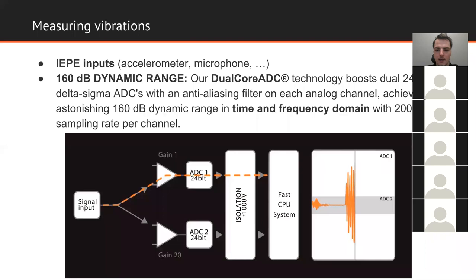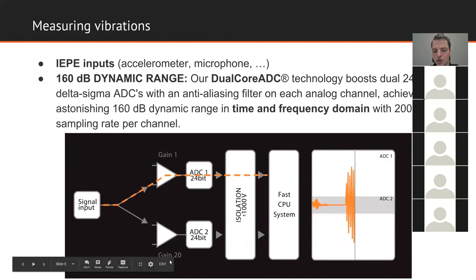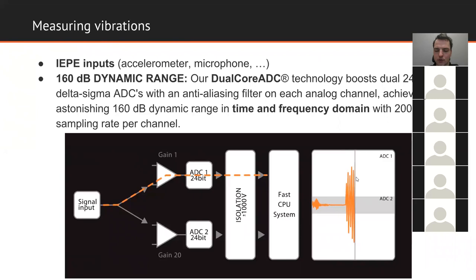The SIRIUS ACC amplifier has a dual core technology, which is a unique feature in Dewesoft. We have two 24-bit AD converters, each taking care of the signal with a different range. If we have a signal with a small range, one AD converter handles it — shown in gray in the picture — and if the signal has a high range, the other AD converter handles it. This is very useful for situations with sudden high-amplitude events, so we don't lose data. With this we can achieve a 160 dB dynamic range in the time and frequency domain.